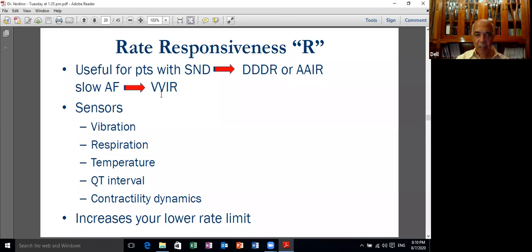How does the pacemaker know that you are exercising? Well, the commonest way is vibration. There is a piezoelectric cell which is welded to the inside of the can of the pacemaker. If you vibrate, it increases the ventricular pacing. And you can vibrate more when you are going down the stairs than when you are going up the stairs, although you need more energy going up the stairs.